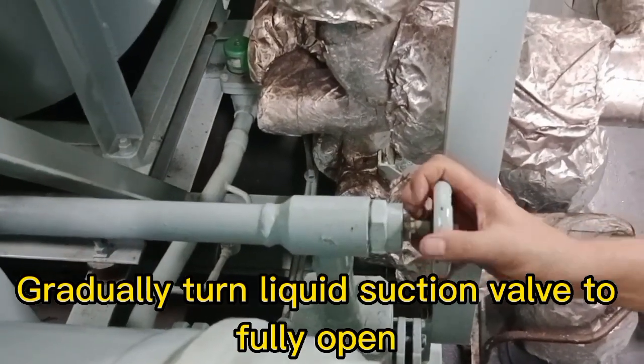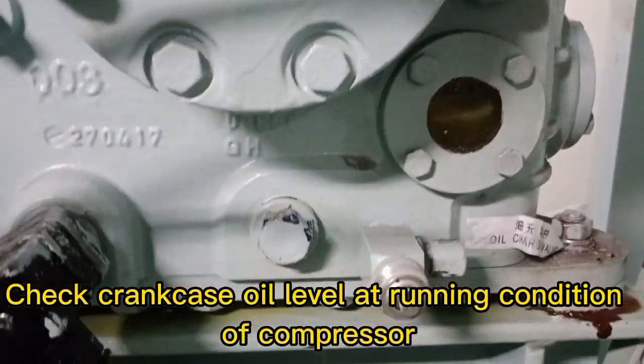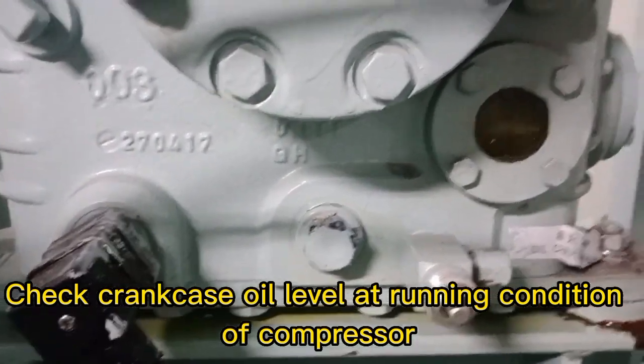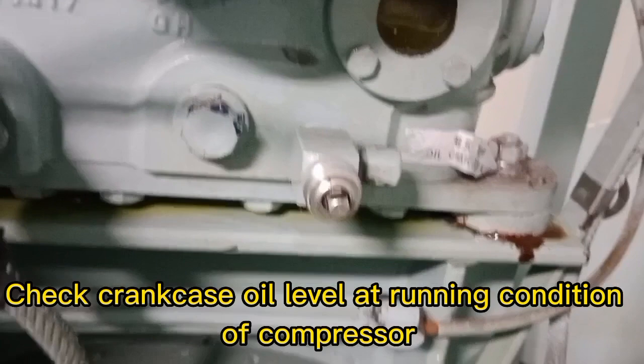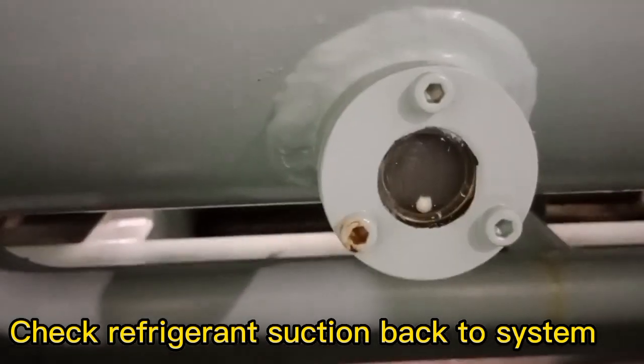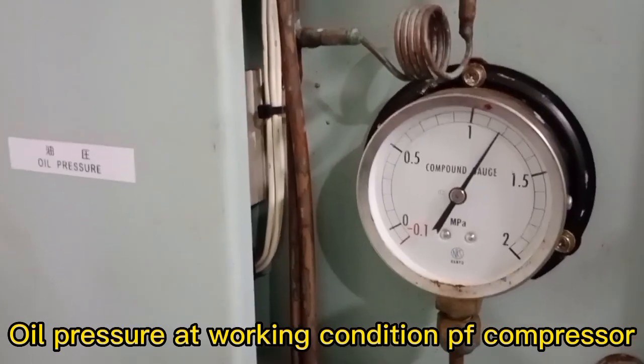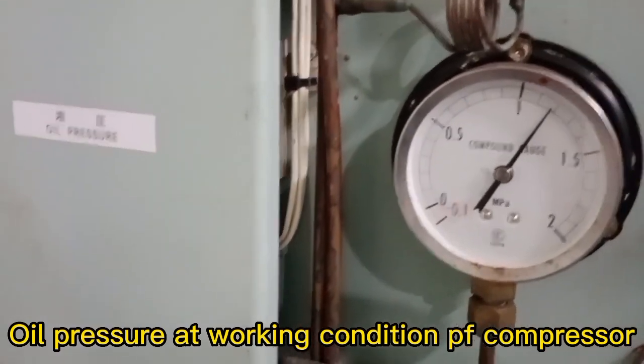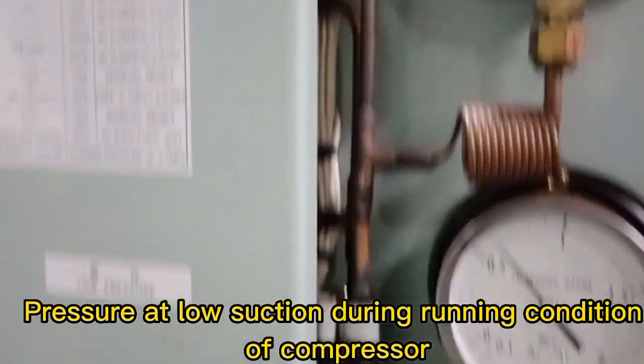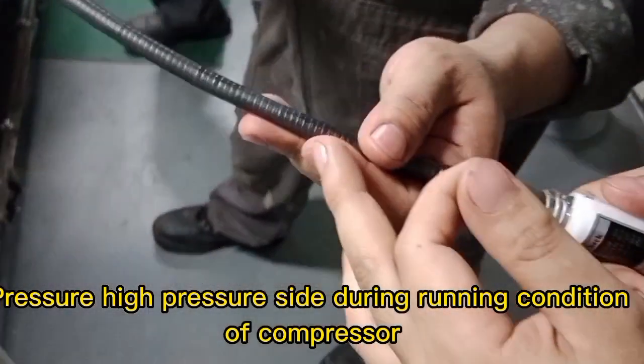Gradually turn the liquid suction valve to fully open. Check the crankcase oil level at running condition of the compressor. Check refrigerant suction back to the system. Observe the oil pressure, low suction pressure, and high pressure side — all during running condition of the compressor.